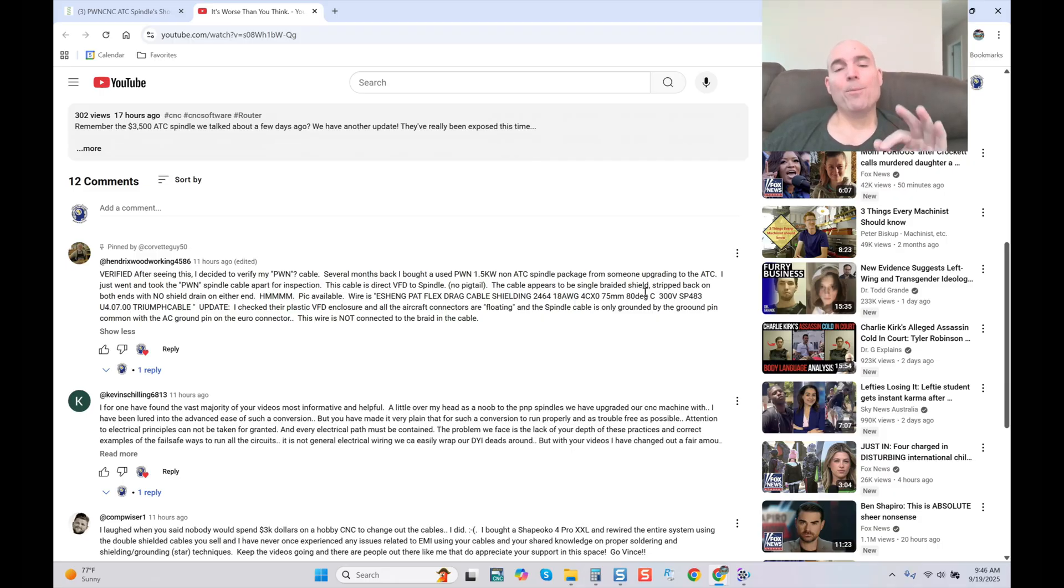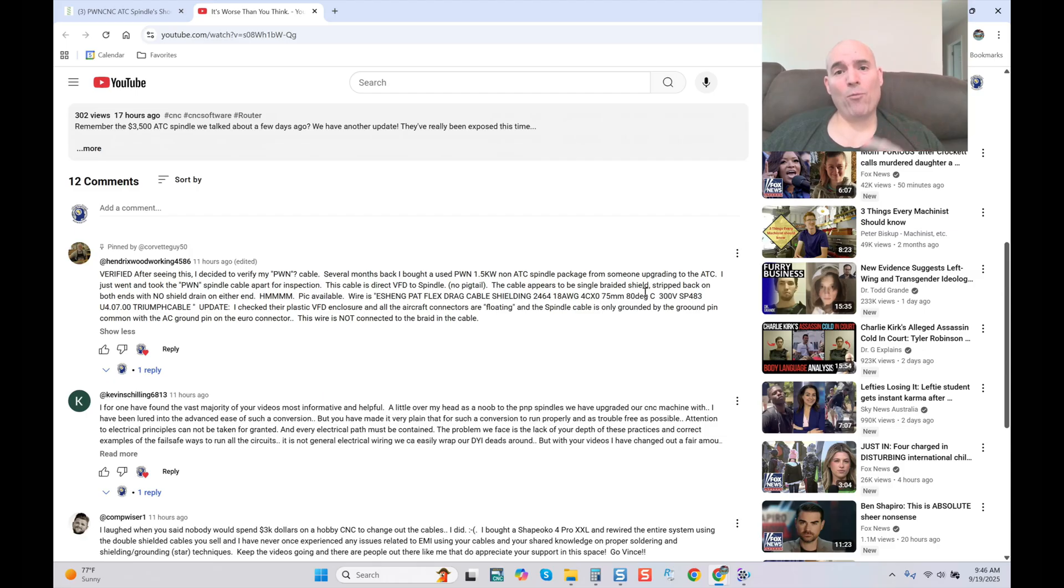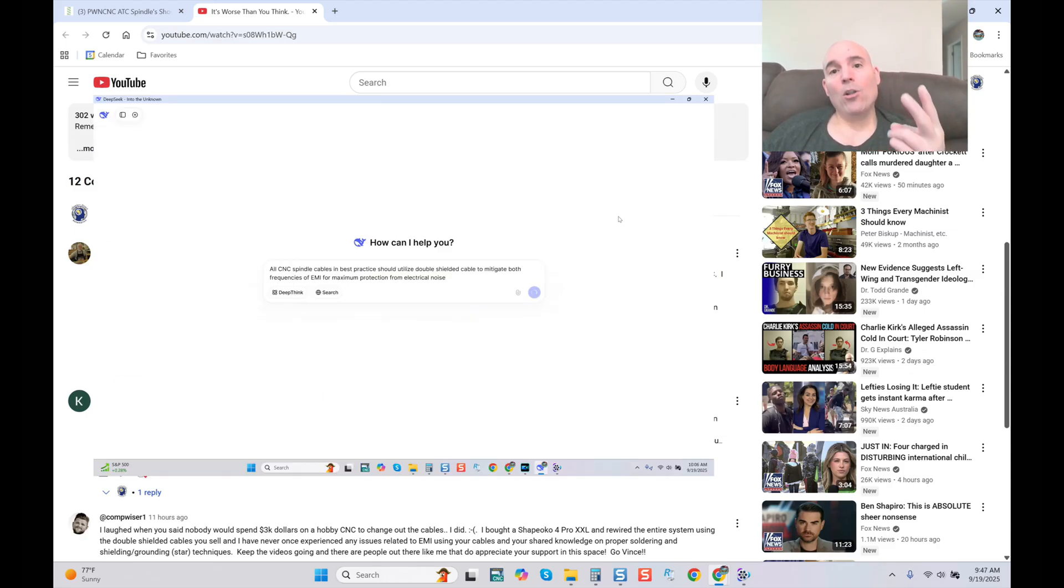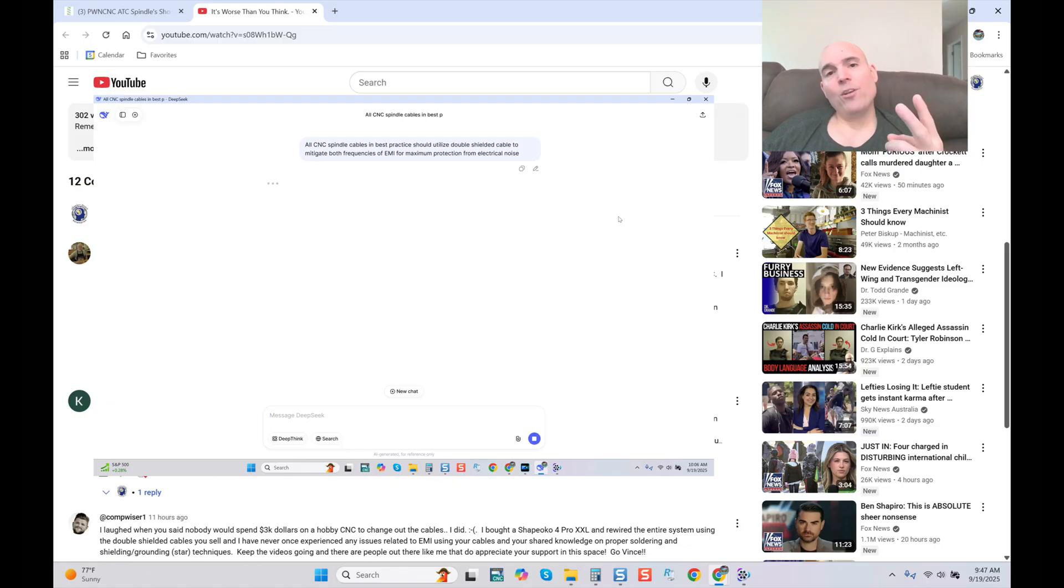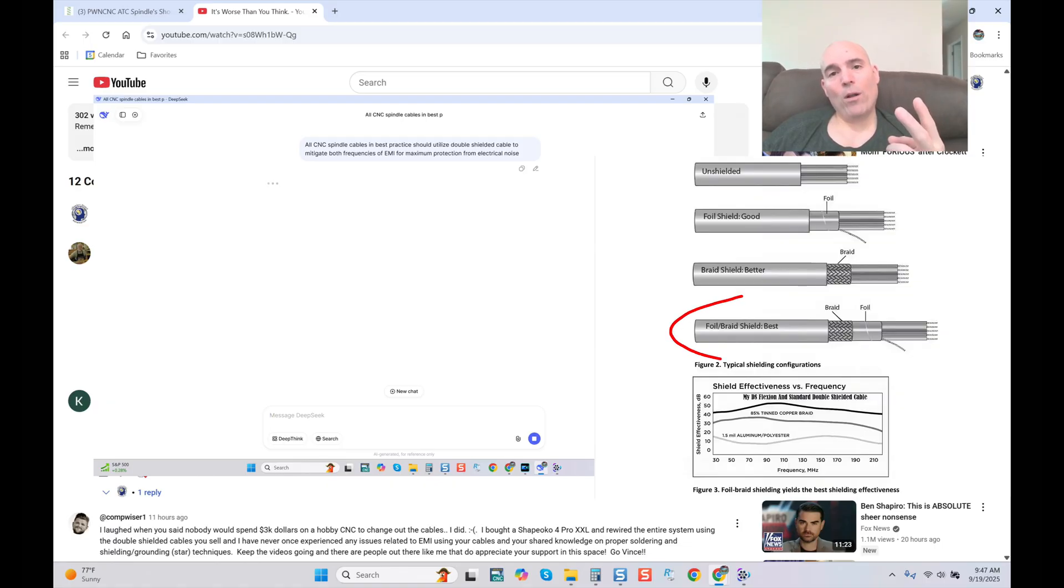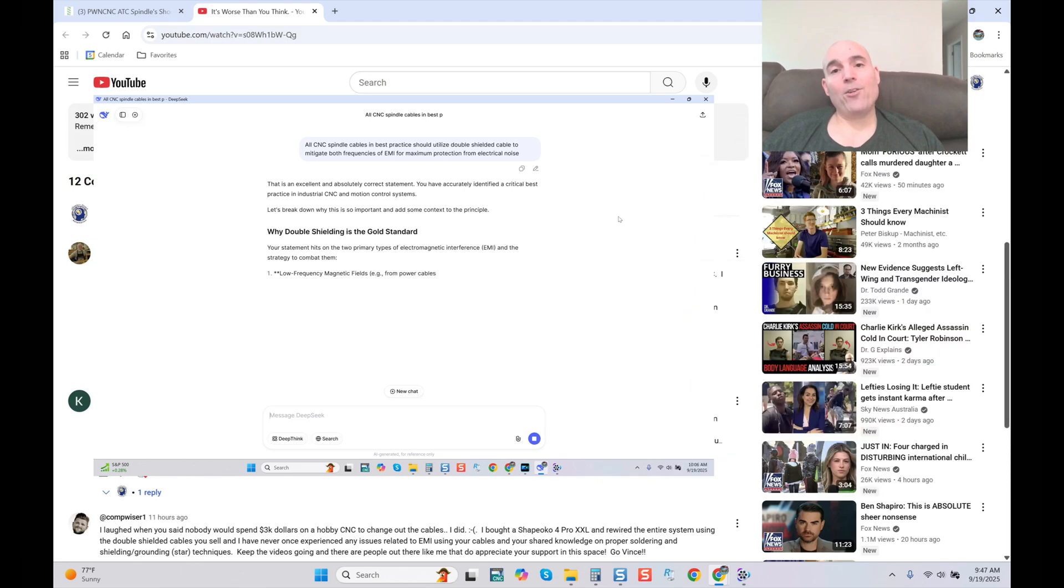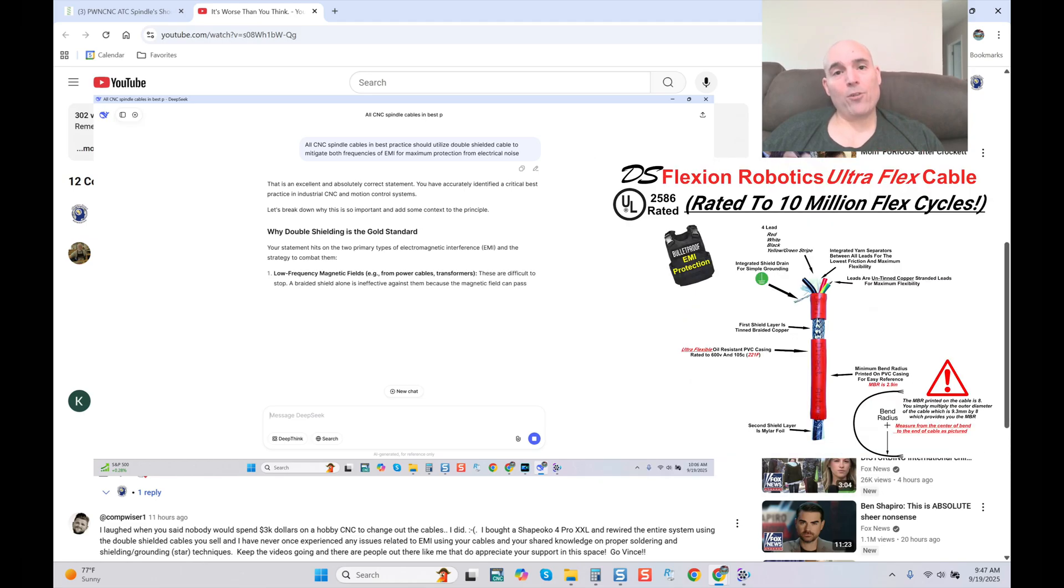All spindle cables, AC, DC, any size, should be utilizing double shielded cable to mitigate both forms of EMI in both high and low frequency, utilizing tin braided copper as an external shield along with an internal shield of mylar foil. And then we should also see a shield drain which allows for easier termination so we can once again terminate to ground to dissipate EMI.